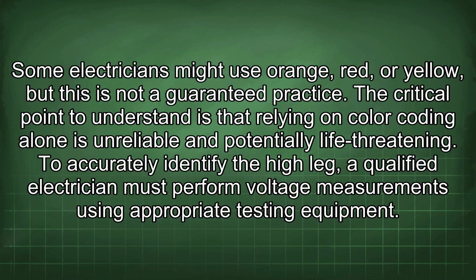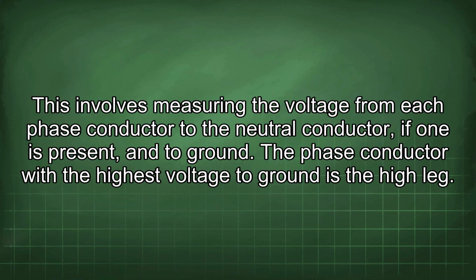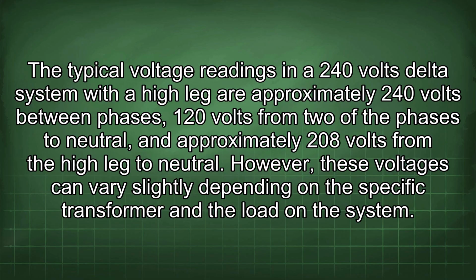To accurately identify the high leg, a qualified electrician must perform voltage measurements using appropriate testing equipment. This involves measuring the voltage from each phase conductor to the neutral conductor, if one is present, and to ground. The phase conductor with the highest voltage to ground is the high leg. The typical voltage readings in a 240 volts delta system with a high leg are approximately 240 volts between phases, 120 volts from two of the phases to neutral, and approximately 208 volts from the high leg to neutral.